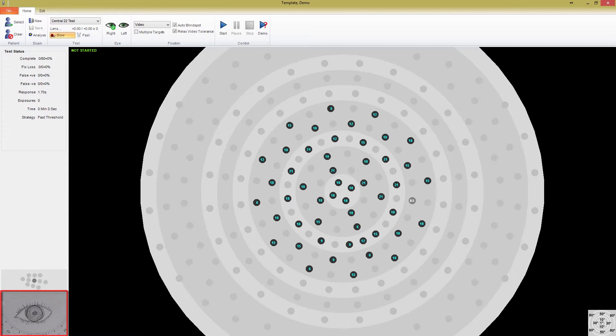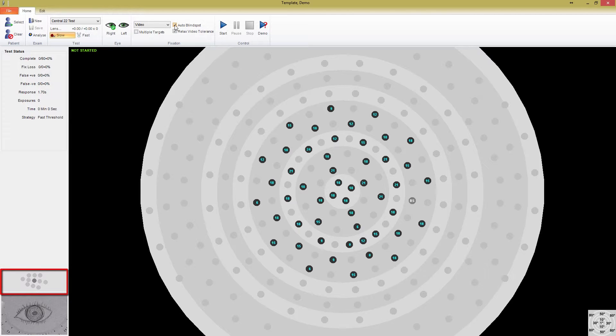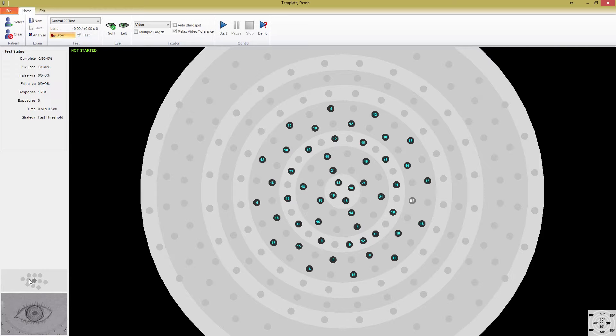In the left corner of the panel, you can select the box for multiple targets to display a four-point set of fixation targets. This can be used for patients with a macular defect. You would instruct them to center their defect within the four points. There's also the auto blind spot option, which you can check on or off. If you look down in the left corner above the video fixation panel, you'll see the blind spot fixation monitoring panel. This displays all of the possible blind spot stimuli in light grey, with the current selected blind spot location in dark grey. With auto blind spot turned on, if the patient sees the blind spot stimulus while fixating correctly, Medmont Studio will automatically select and try other stimulus points to determine the location of the blind spot.